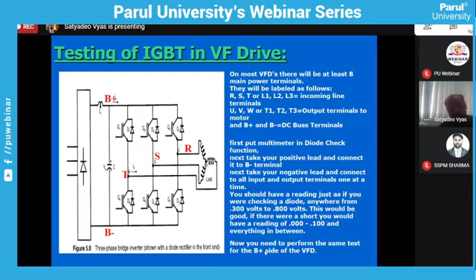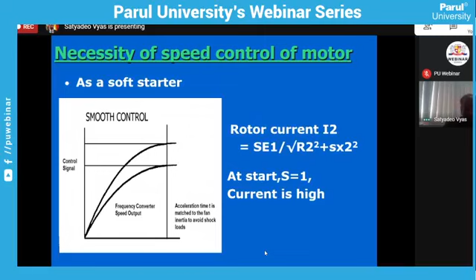Why is speed control required? Speed control of the motor is required for soft starting of the motor as per process requirement. In some processes, speed is required to vary according to the process. So speed control is required, and speed control is again coupled with power saving in some cases. If we are using a soft starter, the motor will start very smoothly without any jerk, and we can stop the motor very smoothly. Thus, it increases the life of the motor, the life of the driven equipment, and also reduces the stress on the electrical network. But this soft starter can't be used for speed regulation or speed control. Only starting and stopping of the motor without any jerk.